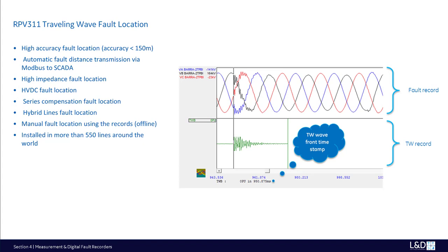The RPV311 TWFL solution is composed of the RPV311 process unit, RA333 high frequency acquisition unit, and RT43X GNSS clock. The highly reliable fault locating system uses an innovative and patented combination of traveling wave and fault detecting algorithm. The typical accuracy can be within 150 meters regardless of line length. Precision is not affected by line and fault impedance, mutual coupling effects, or all compensation circuits like the capacitor bank, so it can be used for various fault locations: high impedance, HVDC, series compensation, and hybrid line, etc.